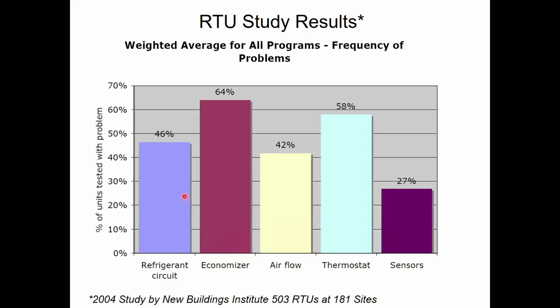So 46% of the units had a refrigeration circuit problem. That typically means either there was a minor leak. If there's a major leak, somebody already fixed that. There's either a minor leak, or the unit was overcharged, or the unit was undercharged. So basically half of the time something's wrong.